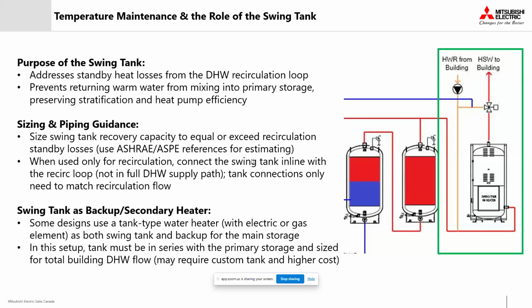Sometimes the swing tank can also double as a backup heater using an electric or a gas element if extra capacity is needed throughout the system. In those cases, it's typically connected in series with the main storage and sized for the building's full hot water demand. If it's just addressing recirculation losses, then it can usually be piped in parallel and sized only for the lower flow of the recirculation loop.